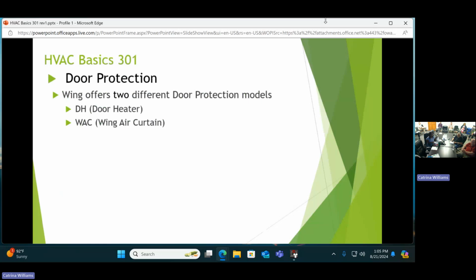It's an air curtain. It puts out a high velocity air from the top down to the floor. That creates a barrier. Keeps dust and bugs away, and it will stop the air from penetrating. That's because you're having that high volume curtain or a barrier. That's the 2 things you get into for door. That barrier will bend with the wind, but it'll stop the wind.